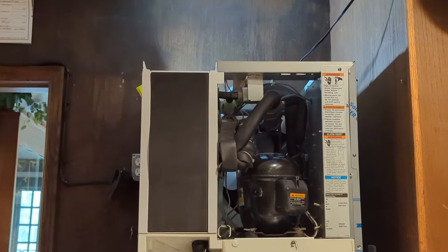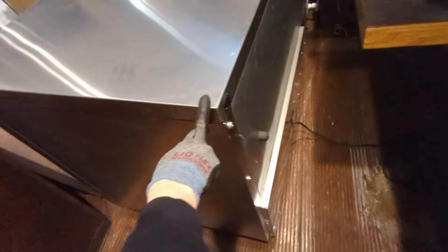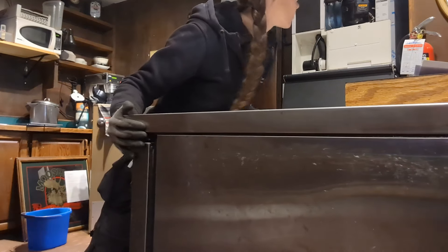While the cleaning solution is circulating, I'm going to check this little under-counter prep cooler. There's a bit of fluff on the outside — little cobwebs — but the coil looks good. I'm going to brush away all those cobwebs, and there was actually a spider in there. I was pretty surprised at how much dust came off that coil — it looked pretty clean but it must have been dusty in there. Anyway, that's done, so I'm going to push it back into its place.